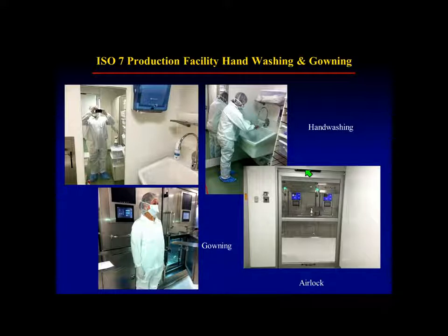But we've gone forward with this, and in the ISO 7, we actually do wear the bunny suits. We do wear masks, face covers. I'm the model here, and this is my engineer, my co-director. And again, what you're doing essentially is going into your airlock area. So all the air from the ISO 7 comes out to the lower grade air.